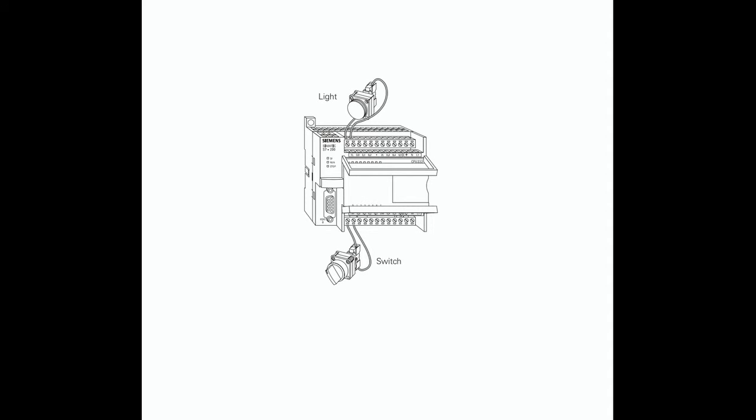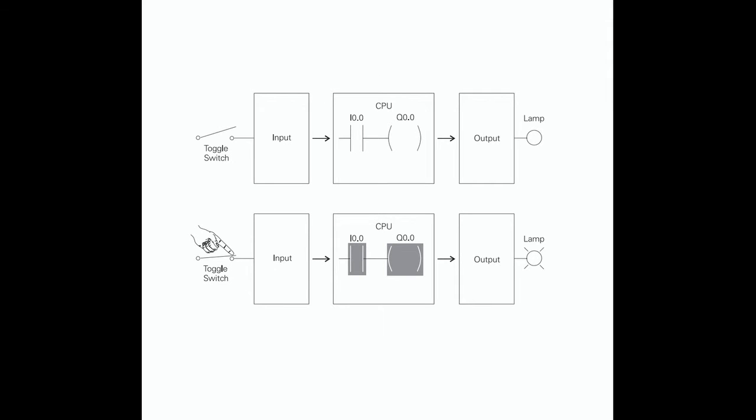Wiring: To accomplish this task, a switch is wired to the input of the PLC and an indicator light is wired to the output terminal. The following drawing illustrates the sequence of events. A switch is wired to the input module of the PLC and a lamp is wired to the output module. The program is in the CPU. The CPU scans the inputs. When it finds the switch open, I0.0 receives a binary 0, instructing Q0.0 to send a binary 0 to the output module and the lamp is off. When it finds the switch closed, I0.0 receives a binary 1, instructing Q0.0 to send a binary 1 to the output module, turning on the lamp.